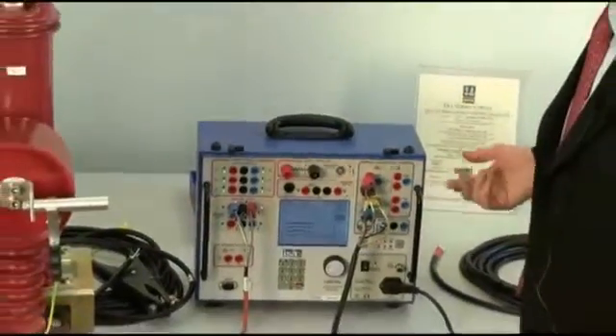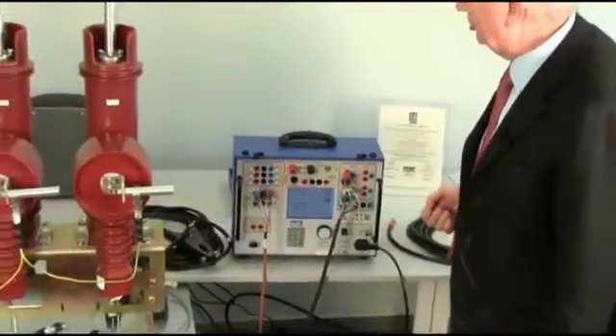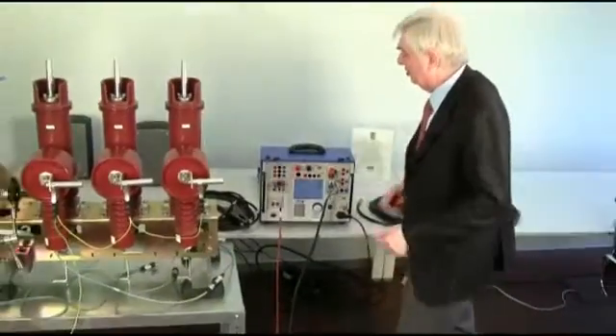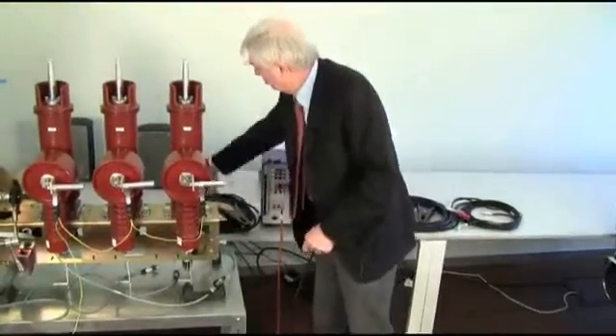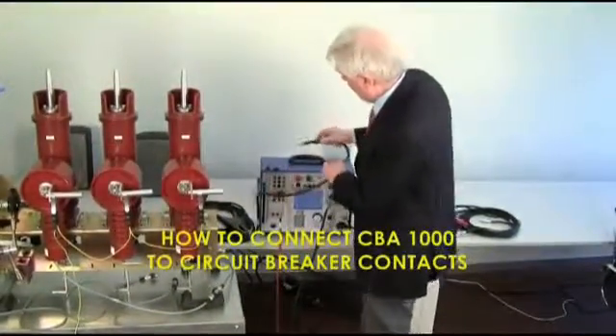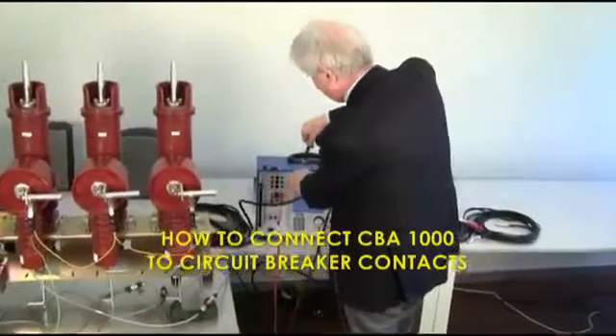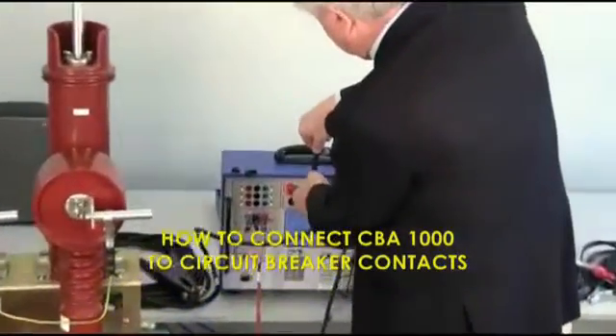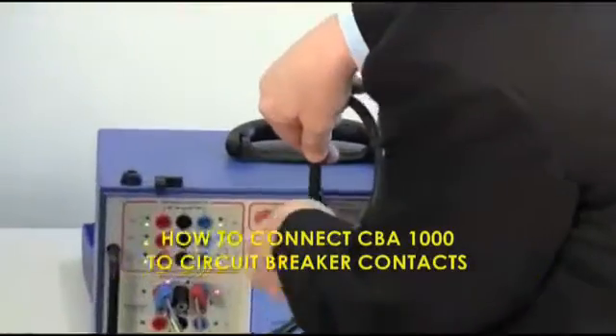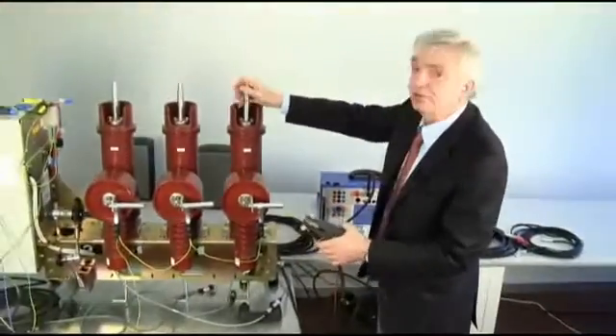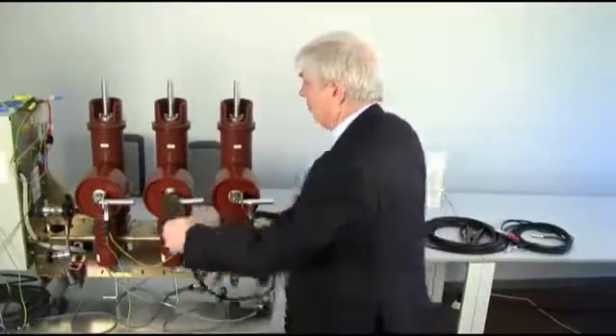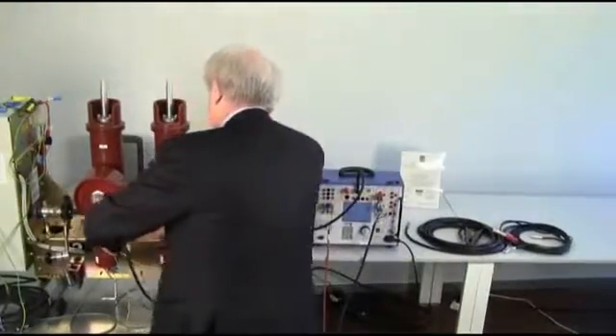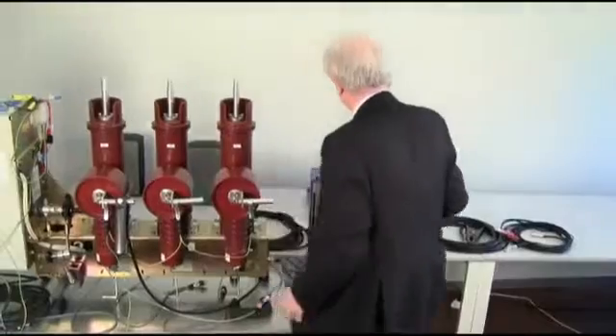The test of the contact resistance is quite straightforward. You have to use our big cables. So this is cable number one, and for instance, I want to measure the contact resistance of this pole, pole C. Or better, I start with pole A, and then you can see.